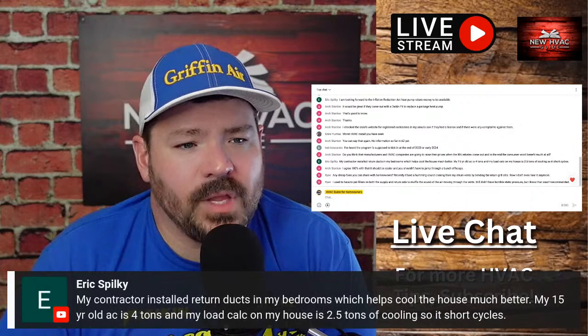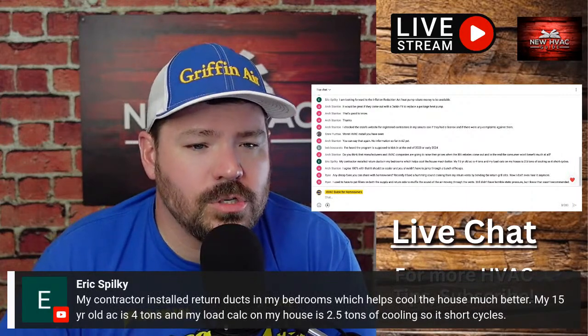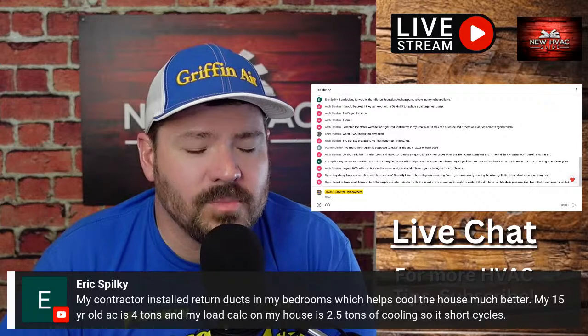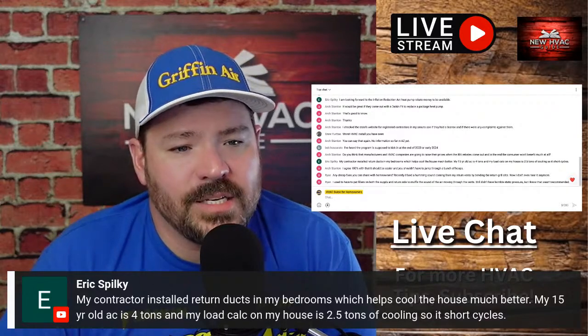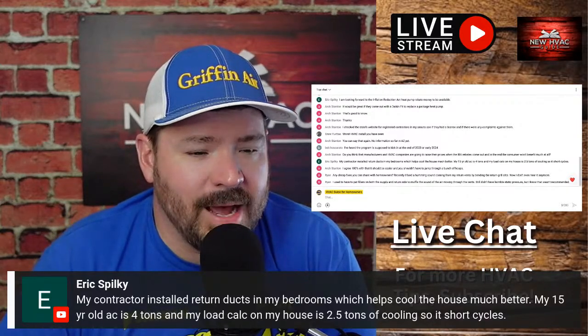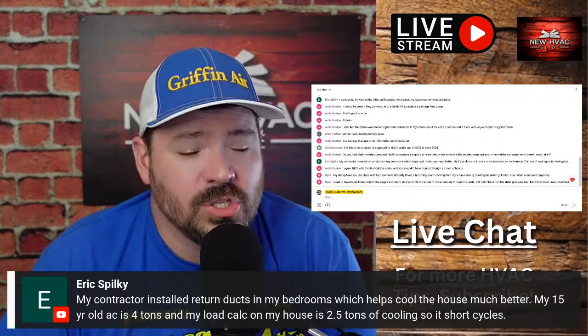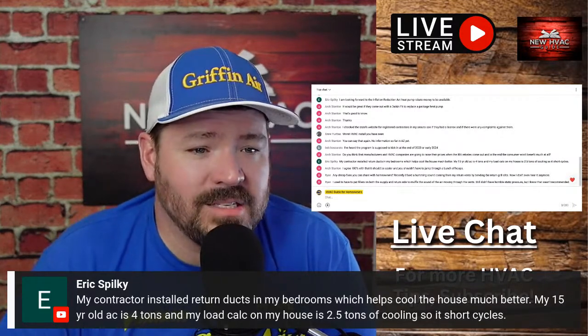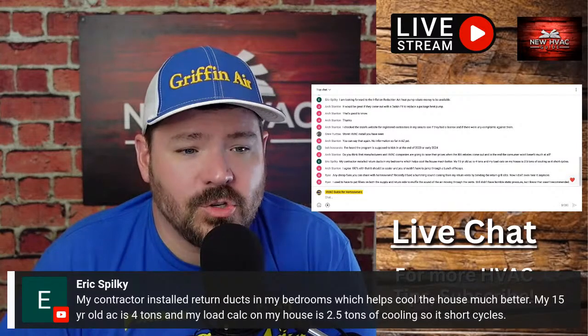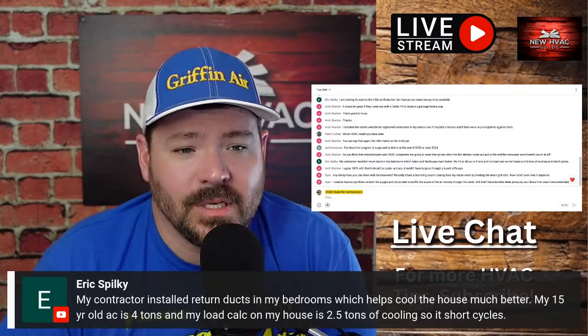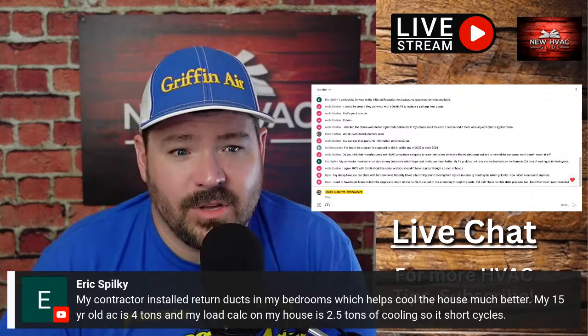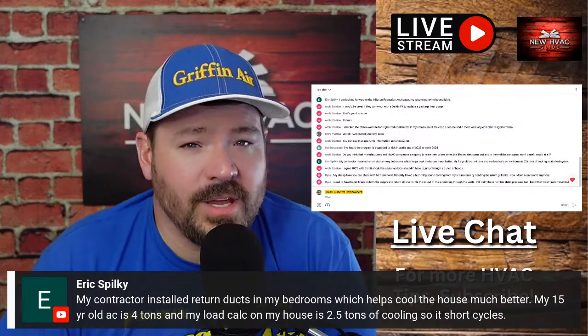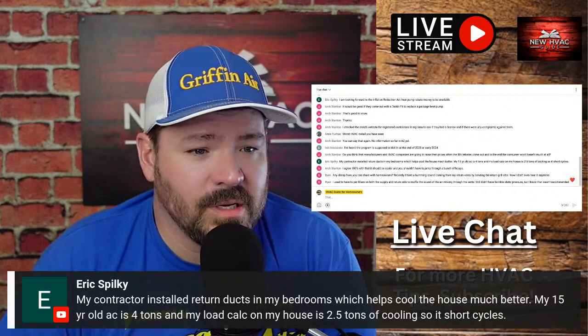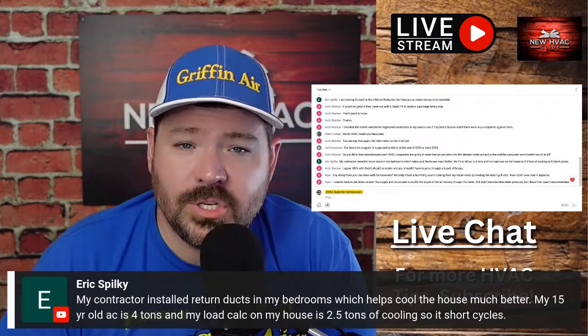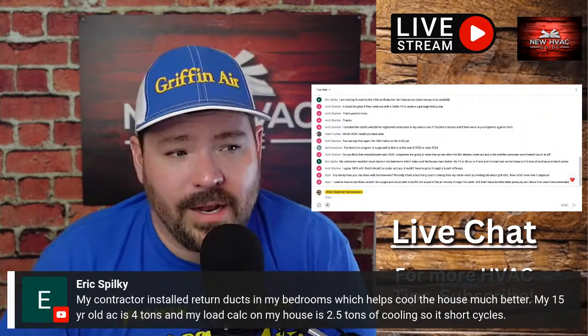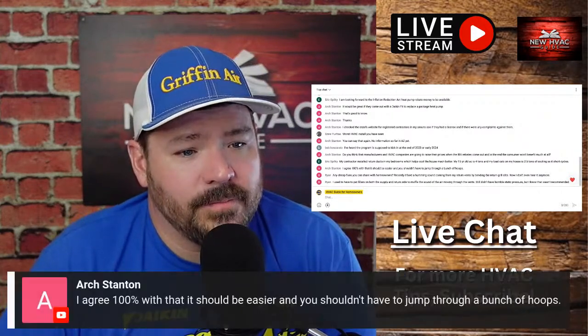It's huge, right? Eric says his contractor installed return ducts in his bedrooms, which helps cool the house much better. His 15-year-old AC is 4 tons, and the load calculation for his house is 2.5 tons of cooling, so it does short cycle. Yeah, 1.5 tons too big is a lot. That's like 1,000 extra square feet in most houses, so it's going to short cycle. You could have humidity issues depending on where you're located in the country. Yeah, that's a shame.